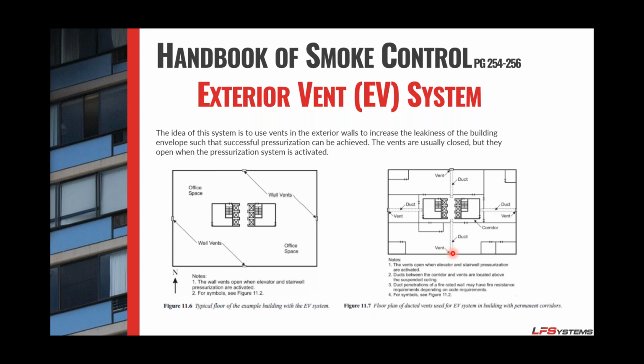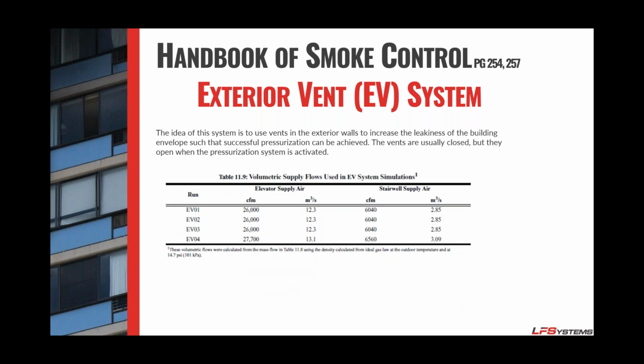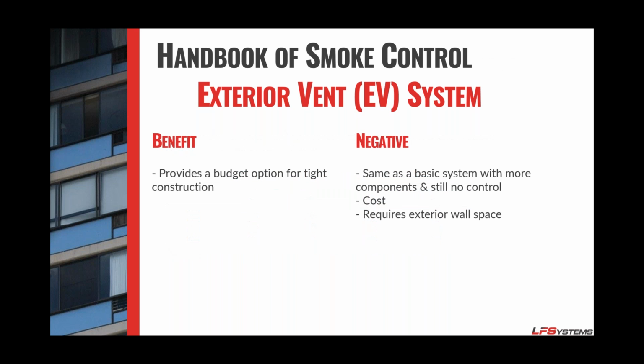So when the fans turn on, it actually starts to push air out through these ducts or through the walls. And this is proven through the CONTAM analysis. The CFM is exactly the same as the basic system. But you still have no control over this. So you have no way of knowing what the pressure will be under all conditions. So again, it provides a budget option for a tight construction, but it's the same as the basic system with more components and still no control, which means it actually does cost some more because you have all those dampers. And that's assuming that your architect or your building designer will allow you that much wall space for the dampers and that much ductwork space in the ceilings.